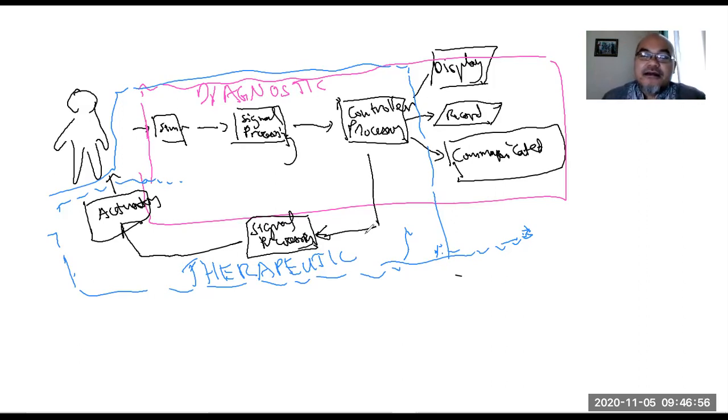But more recently, for example with the implantable ventricular defibrillator, the system first acquires information from the body with a certain sensor. So this is the traditional therapeutic approach, where there is no sensing function inside the instrument, just one-way information from a controller or processor to the patient's body with an actuator.